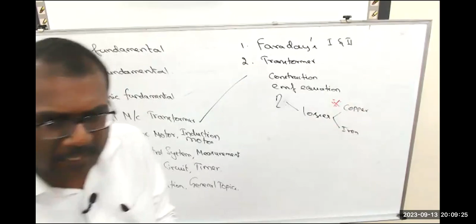At the same time, we discuss the regulation. For example, in the MAP, we are using a 1600 kVA transformer, so the capacity of the transformer is 1600 kVA. In the secondary, we need to get 1600 kVA, but instead we are getting only 1500, which means we have losses. The secondary of the transformer is 415 volts or 240 volts. For understanding, we take 240 volts. We are expecting 240 volts, but we are getting only 220 volts. So what is the difference? 20 volts. How do we calculate this difference? We go for the regulation.